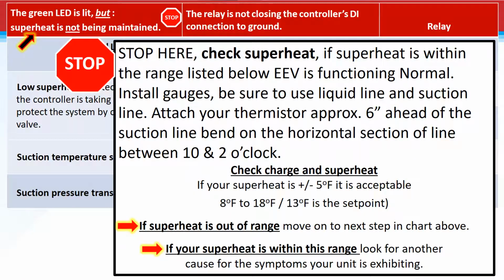If the green light is lit, but superheat is not being maintained, or we don't think it is, we need to stop right here and check the superheat. If it's within range listed below, that's between 8 and 18 degrees, the EEV is functioning normally.